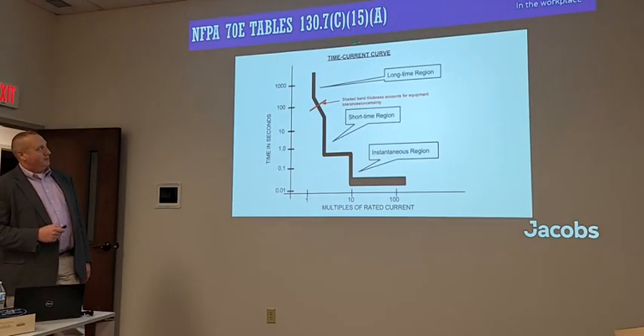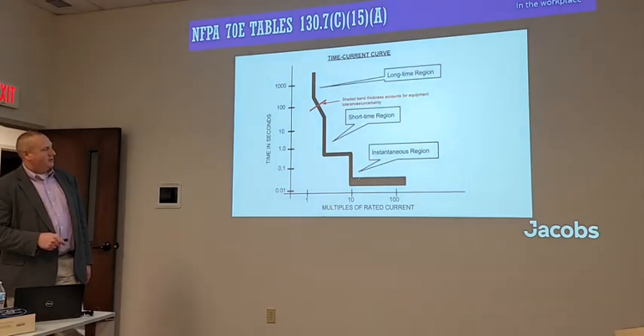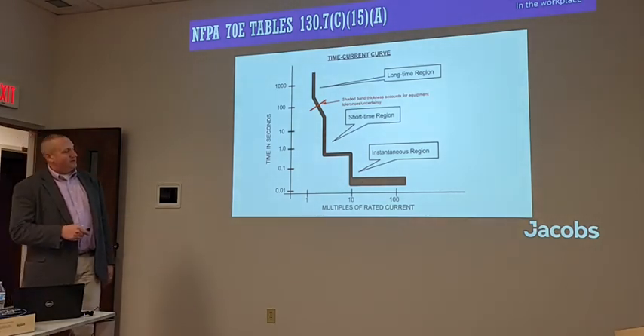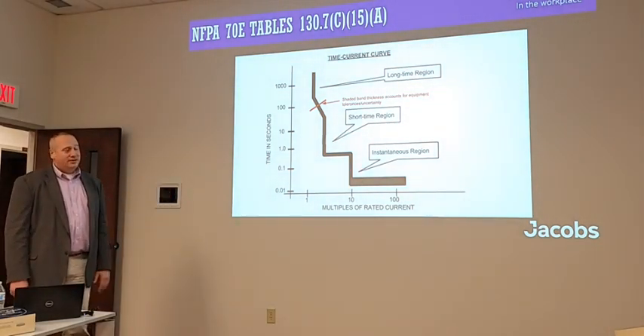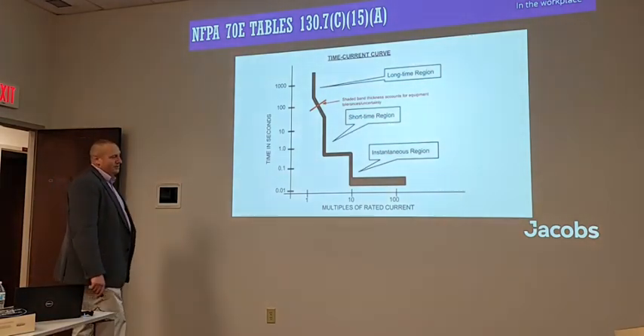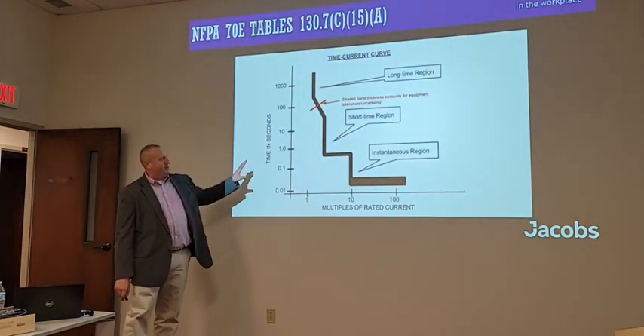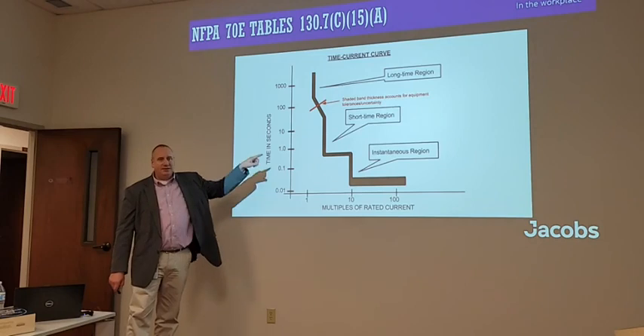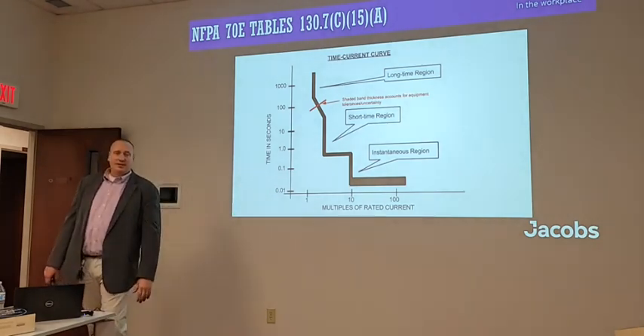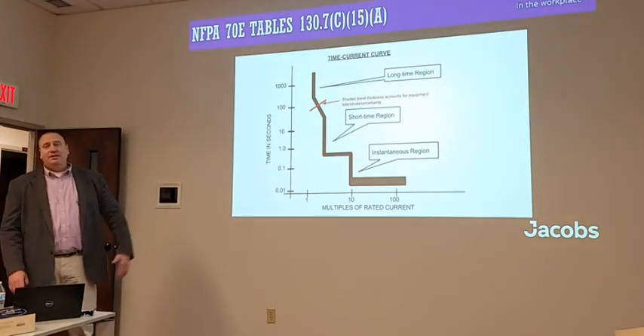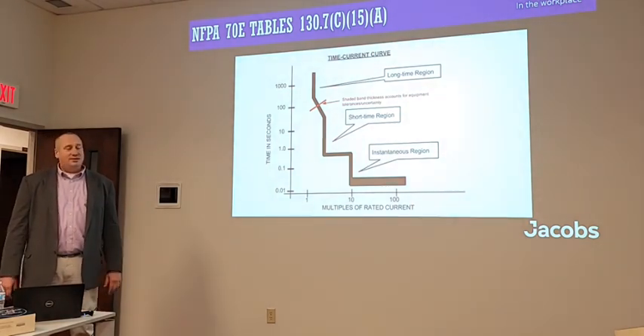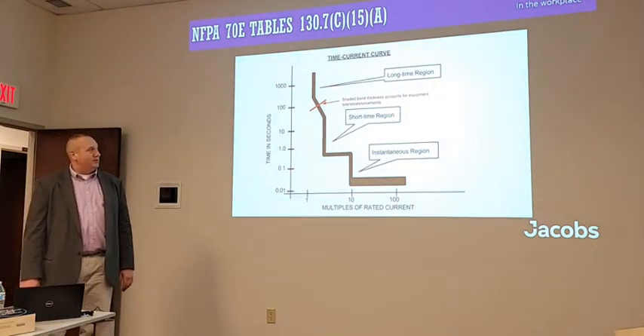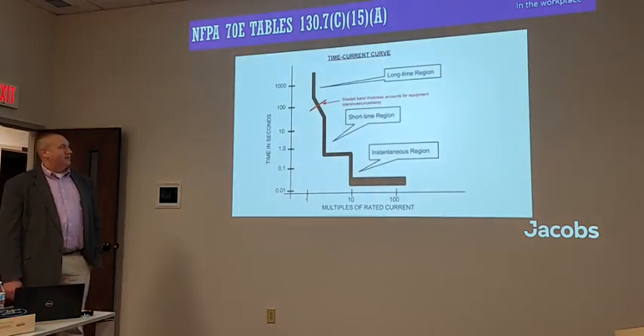For those, if you're not familiar, this is a time current curve. You've got your time in seconds, your current here, so instantaneous high current is going to cause it to trip quickly. So if you have this, you can tell how quickly it's going to respond on a breaker. And some of the newer equipment is nice, like some of the 480 volt breakers have the settings that are set up in these different scenarios. So if you know what you're looking at, there are some newer equipment where you could maybe collect this information out in the field to make an educated decision on what PPE to use.